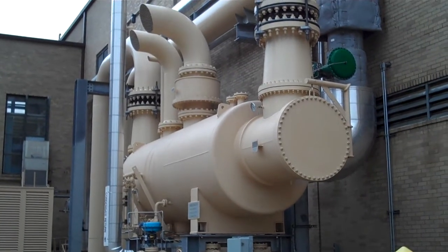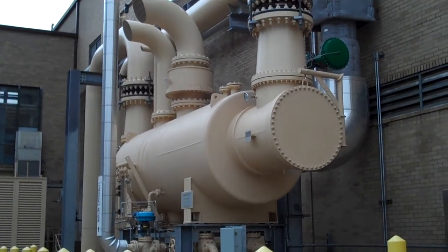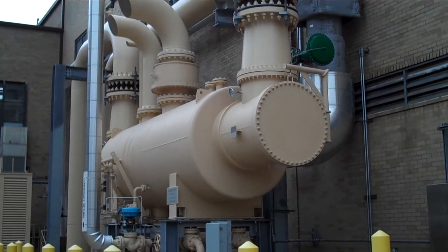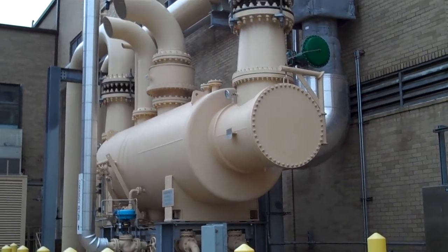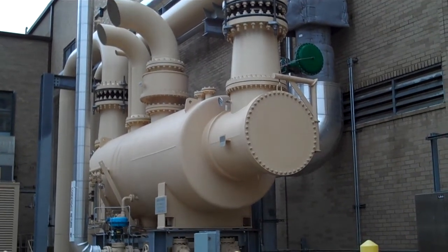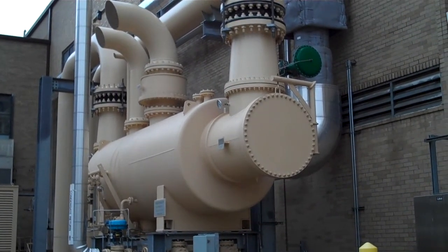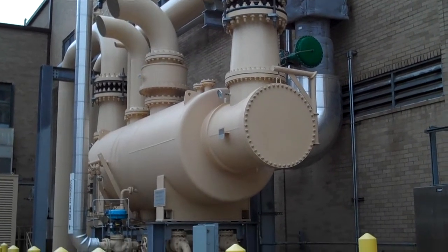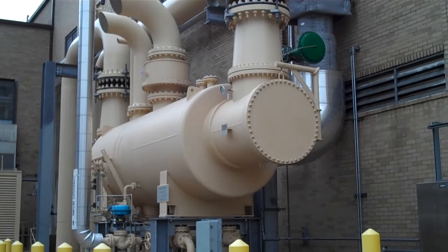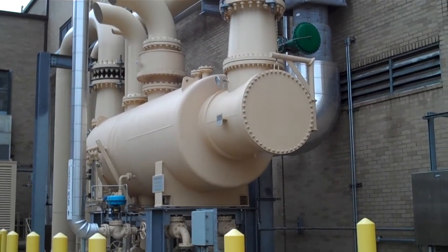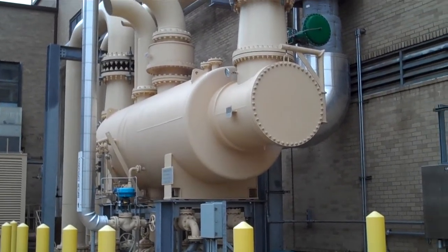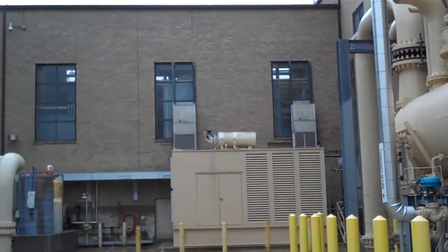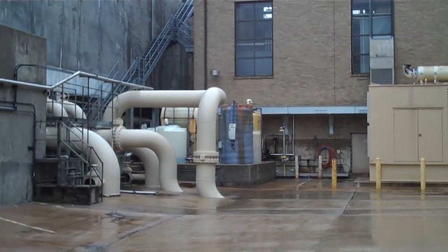What basically happens is you have condenser water going through it from the tower, and you basically knock the temperature out of the steam and condense the steam. If we need to have a false load for something in the system though, we can dump 20-pound steam in here and generate a load, so to speak, because it's all about supply and demand when you deal with the 600-pound system, 60-pound system, and 20-pound system in this plant.